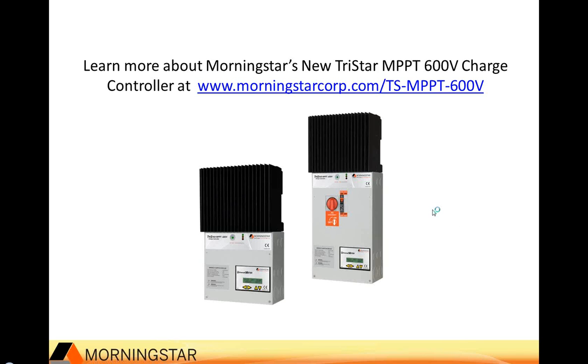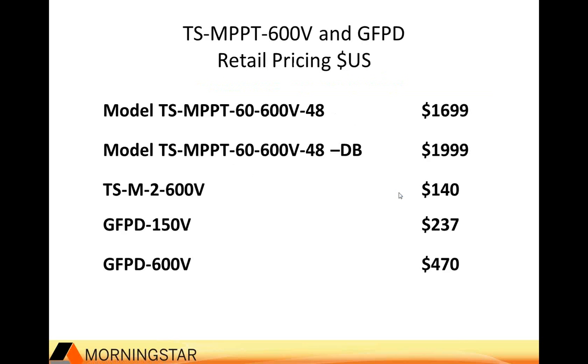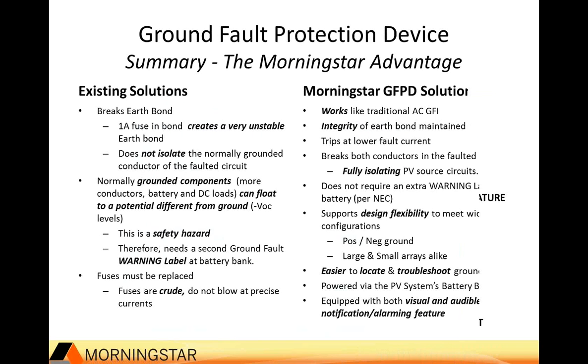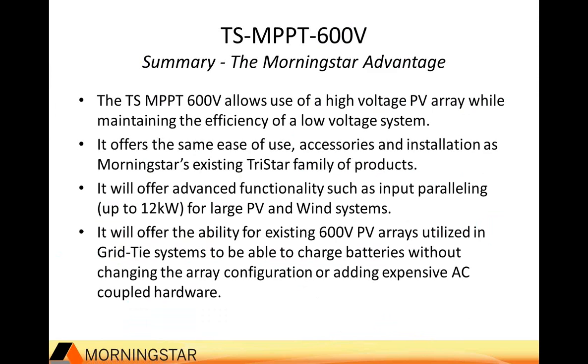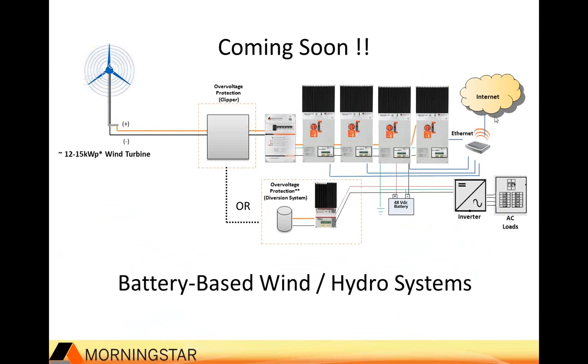One question about the advantages of paralleling versus segmenting charge controllers. When you have a design, let me jump back to this slide. One of the benefits of combining the controllers together is that in this case, in a wind turbine, this is really the only way you can get charging at all, because you have to basically create a 12 kilowatt charge controller. So in this case, it's the only solution you have. If you wanted to do it with a larger pre-combined solar array, you could do that as well. But when you do that, it's going to track it as one giant array. So that gives you some new functionality and the ability to take a wind turbine in at 300 volts DC and charge a 48-volt battery.